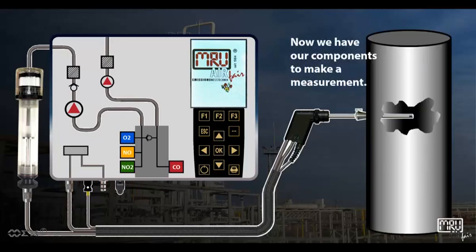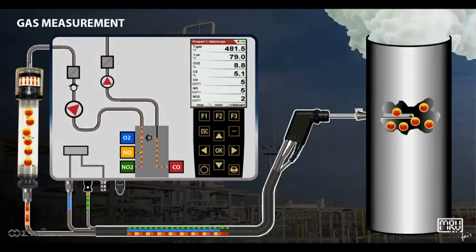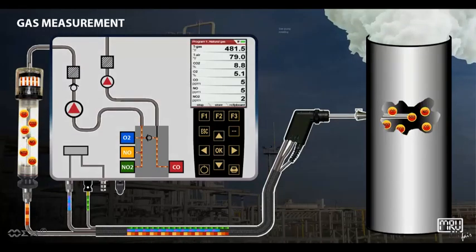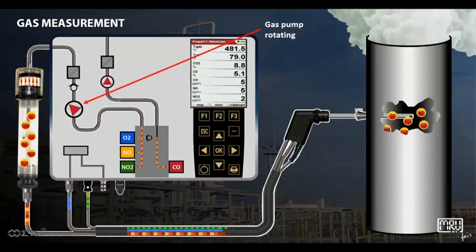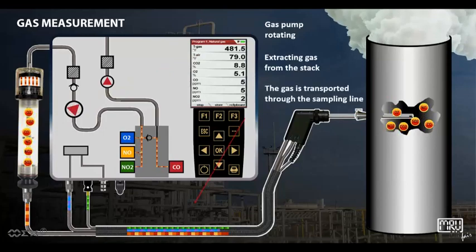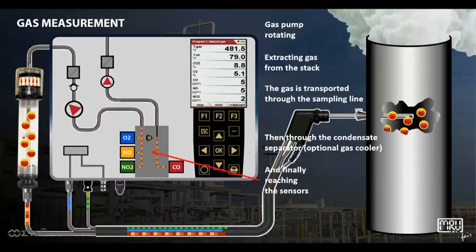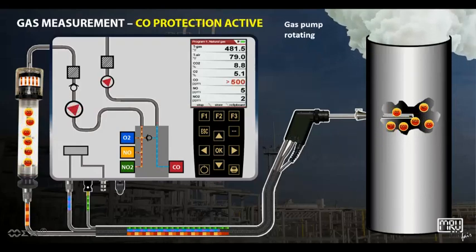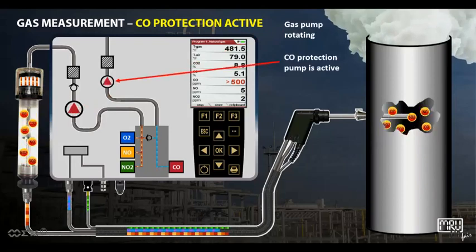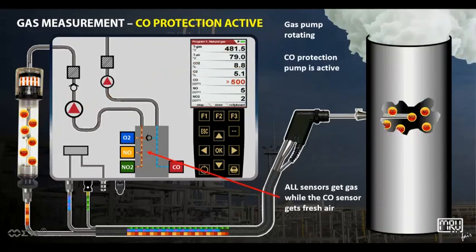Now we have our components to make a measurement. The gas pump rotates, extracting gas from the stack. The gas is transported through the sampling line, then through the condensate separator and optional gas cooler, and finally reaches the gas sensors. When CO protection is active, the CO protection pump is also rotating — all sensors get gas while the CO sensor gets fresh air.